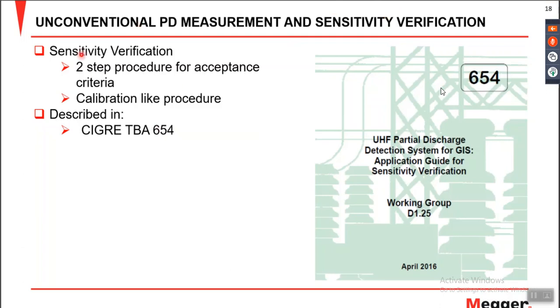For that there is a special sensitivity verification procedure derived by the CIGRE working group, and it is called 654. This particular document is freely available on the CIGRE website. You just need to register with your mail ID on CIGRE, and then you can download this document free of cost. It is a very useful document, and you should read about the sensitivity verification procedure.